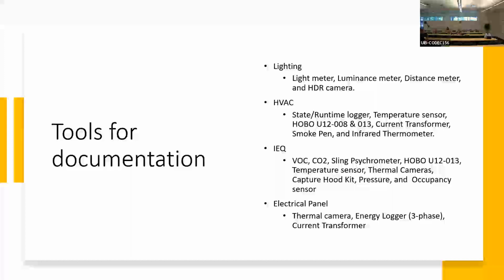Light meter here. You want to open it up on the table, don't take off the cap, turn it on. It's a validation metric, so if you turn it on and look at it, it should read 0. And so it does. You're gonna take it off, and then step away from the light meter sensor.